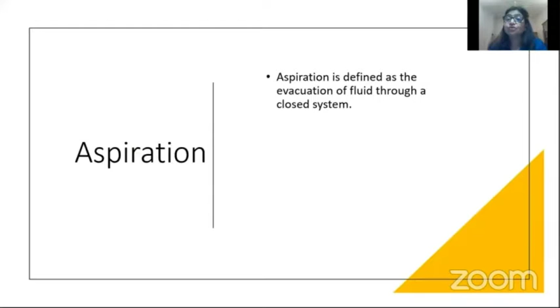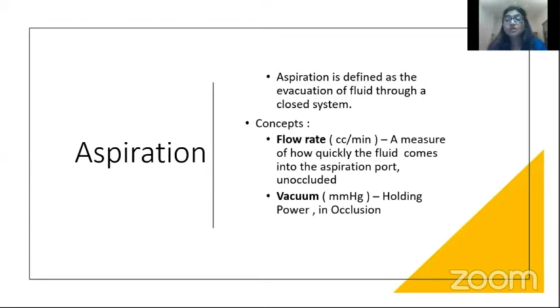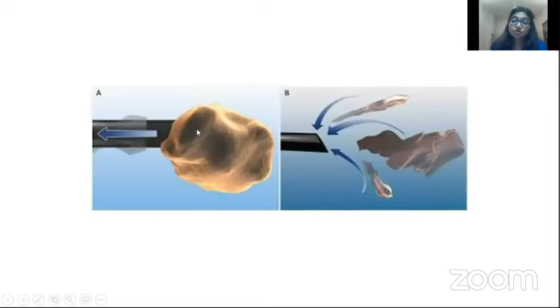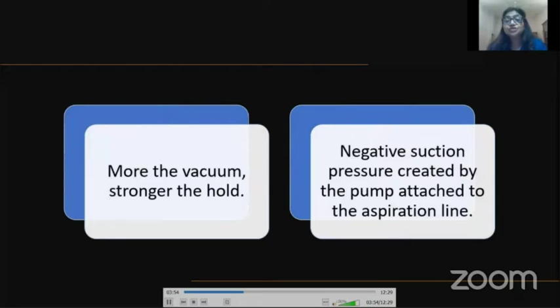And mind you, it is unoccluded, whereas the vacuum is basically the holding power of the tip, and that is measured in millimeters of mercury. Usually the vacuum will build up once there is occlusion of the tip by the nuclear fragment. This is how a flow rate will help to bring the pieces towards the tip, and once the nuclear fragment occludes the tip, this is where the vacuum starts building up. More the vacuum, stronger is the hold of the nuclear fragment, and a negative suction pressure is created by the pump, which is attached to the aspiration line.